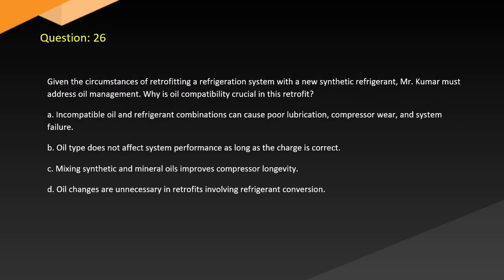Question 26. Given the circumstances of retrofitting a refrigeration system with a new synthetic refrigerant, Mr. Kumar must address oil management. Why is oil compatibility crucial in this retrofit? A. Incompatible oil and refrigerant combinations can cause poor lubrication, compressor wear, and system failure. B. Oil type does not affect system performance as long as the charge is correct. C. Mixing synthetic and mineral oils improves compressor longevity. D. Oil changes are unnecessary in retrofits involving refrigerant conversion.